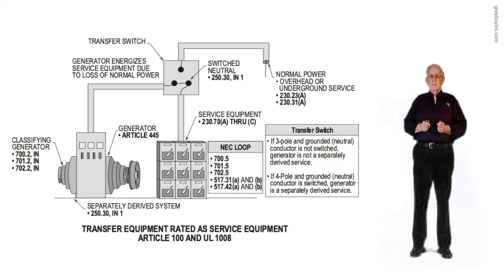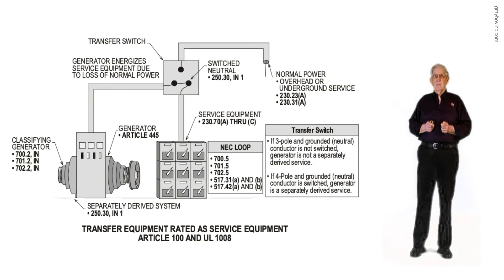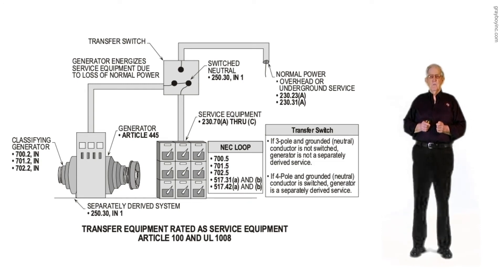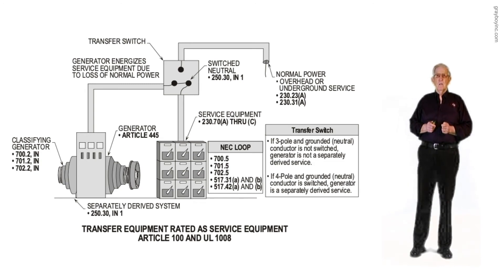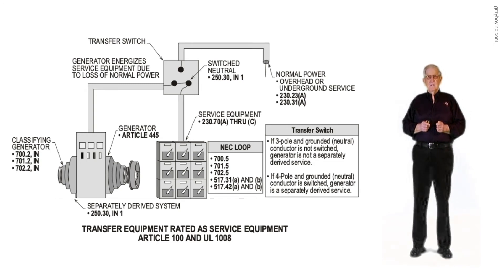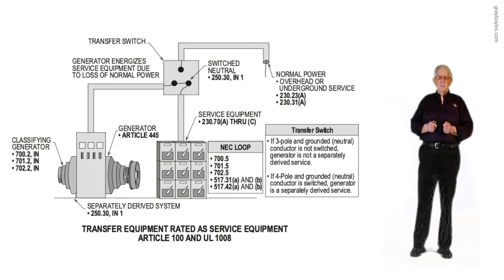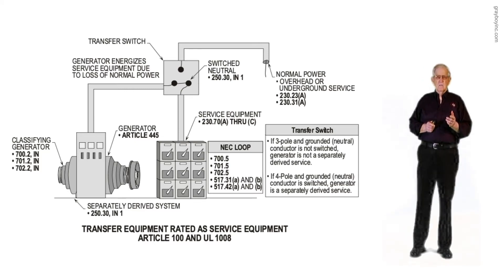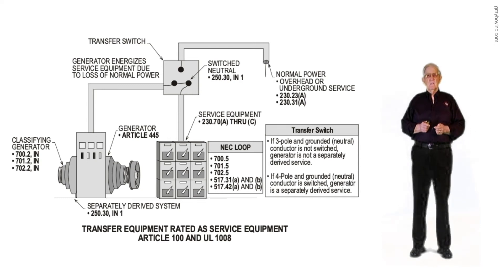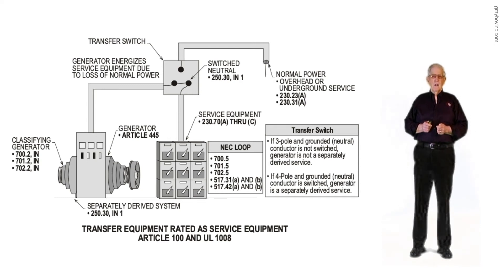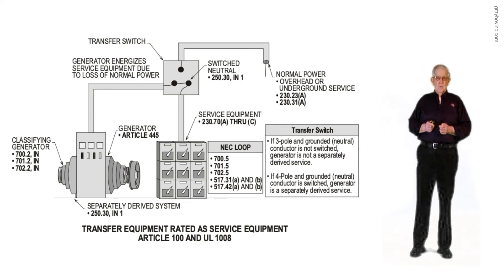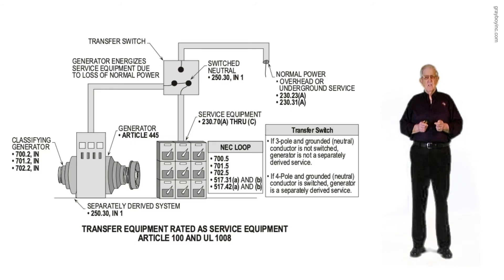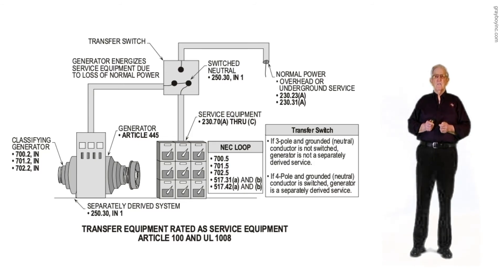For normal power — overhead or underground — for this type of service, you'd find the rules in 230.23A or 230.31A. The service equipment, disconnects, and how they would be arranged — one main or two to six mains — is covered in 230.70A through C, 230.71, and 230.72.